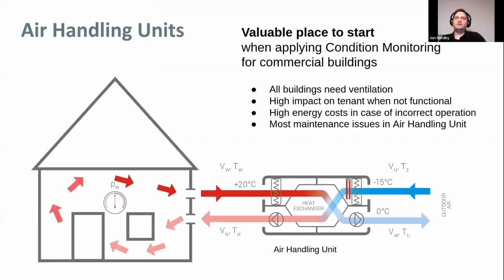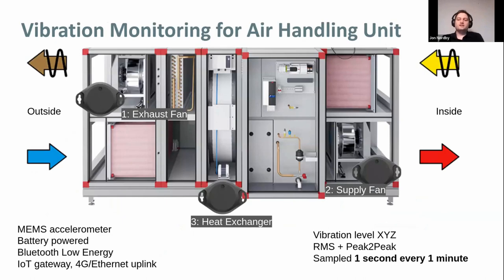When coming to commercial buildings, we did dialogues and research with our customers to find out what is a good place to start applying this technology. We found that the air handling units of ventilation systems are a very good place to start because all buildings need ventilation, there's a high impact on the tenant when the system doesn't work — the air gets bad very quickly — as well as high energy cost if they are running when they shouldn't or running incorrectly. Many maintenance issues regarding ventilation systems are found in the air handling unit, which is a centralized component. A modern type for balanced ventilation has three rotating components: an exhaust fan, a supply fan, and a rotating heat exchanger motor.